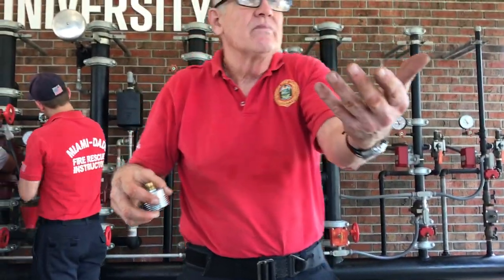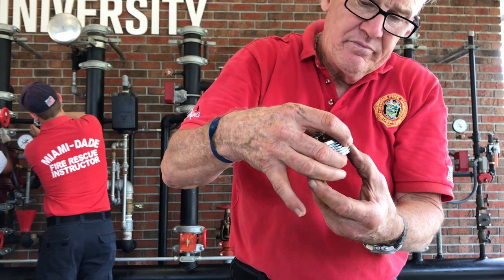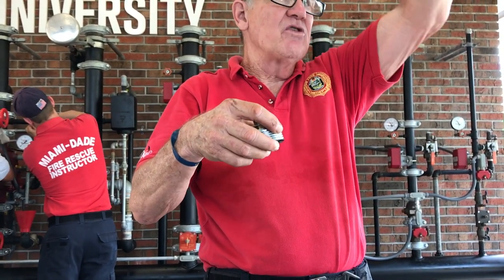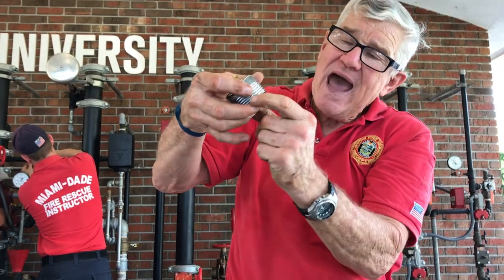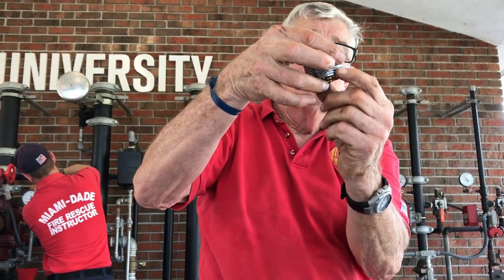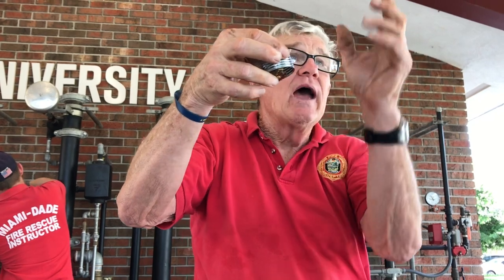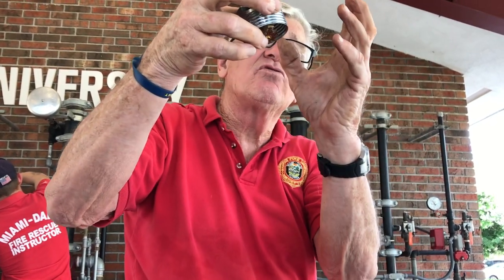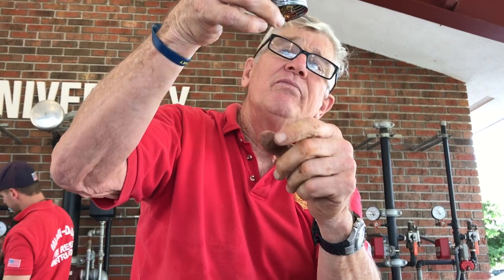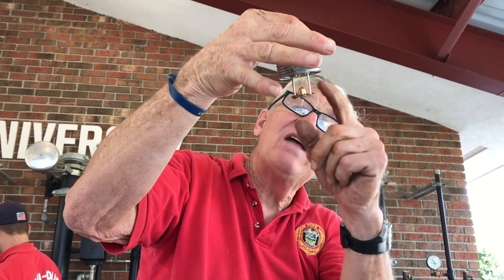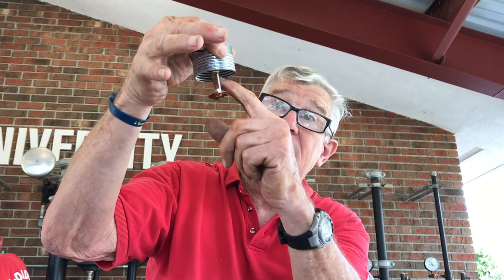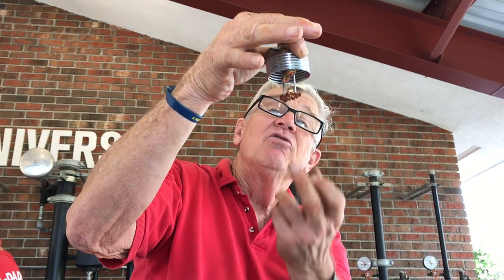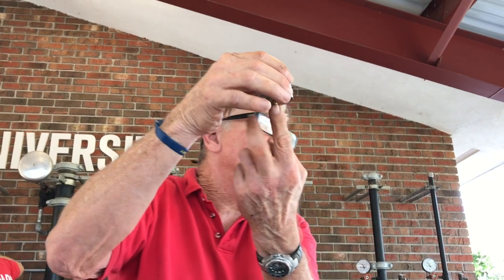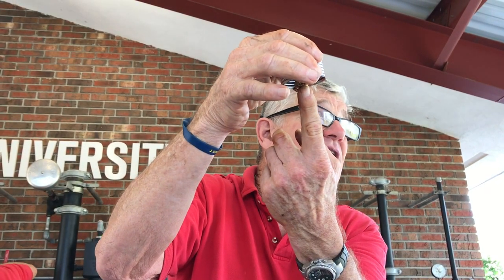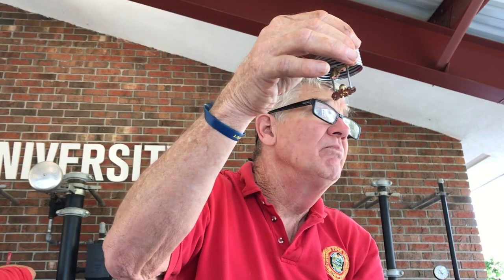This is a recessed head. You see these in our classroom that we were in this morning. You have a white decorative cover that is attached by solder to the sprinkler head. At about 135 degrees, that solder melts, the deflector drops down, and of course the bulb has already been activated. So again, 135 degrees, the cap melts the solder, cap comes off, boom.